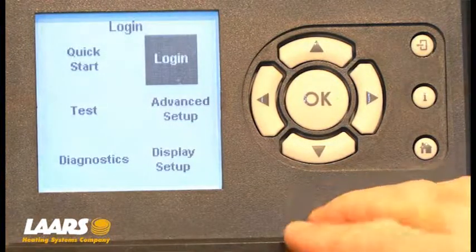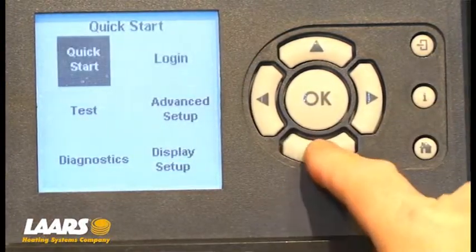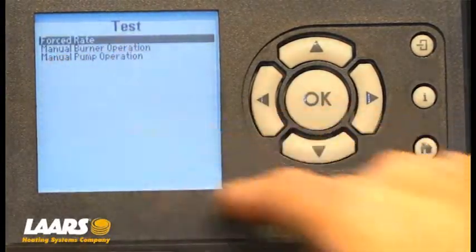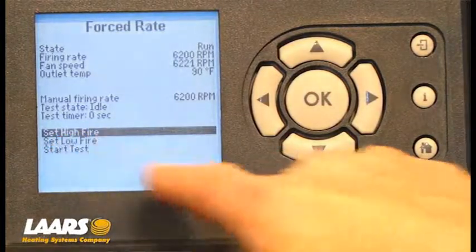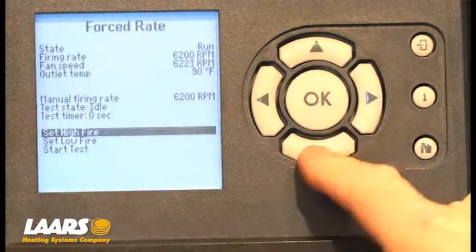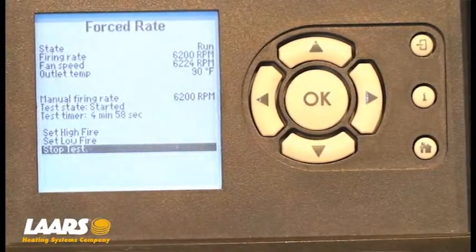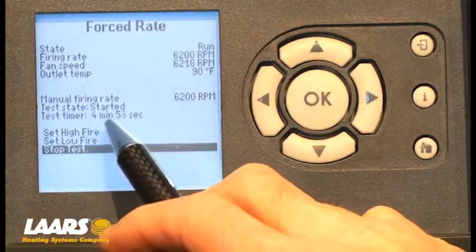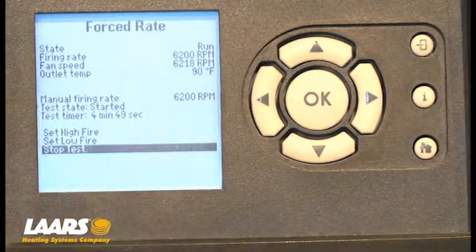Now to do combustion setup, we want to go over to test. Use the left-hand arrow and then the down arrow to test, press OK. The forced rate is highlighted — press OK again and it brings us into the forced rate screen. From here we have set high fire highlighted. Click OK, scroll down to start test, click OK again. Once we start test, our test timer appears and counts backwards for five minutes. Now we have five minutes to dial in our CO2.